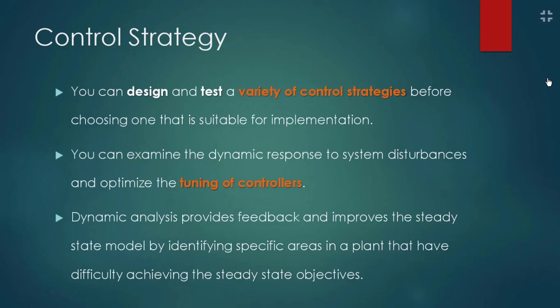You can also examine the dynamic response to system disturbances and optimize the tuning of controllers. For each controller you have tuning parameters — for PID controllers: P, I, and D, or KC, TI, TD — these parameters affect the response of the controller to disturbances. Whenever a disturbance happens, the tuning parameters affect how fast or slow the controller response is. You can test several tuning values and see the impact in dynamic simulation before testing it on the actual plant.